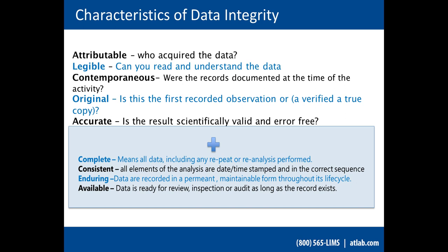Additional ALCOA extensions that have been added over time include: Complete — is all the data, including any reruns, linked to that sample point? Consistent — are all elements of the analysis date- and time-stamped and in the correct sequence? Enduring — is the data recorded in a permanent, maintainable form throughout its lifecycle, backed up, and has anyone checked the backup to ensure it's still retrievable? And Available — is data ready for review, inspection, or audit as long as that record exists in the database?